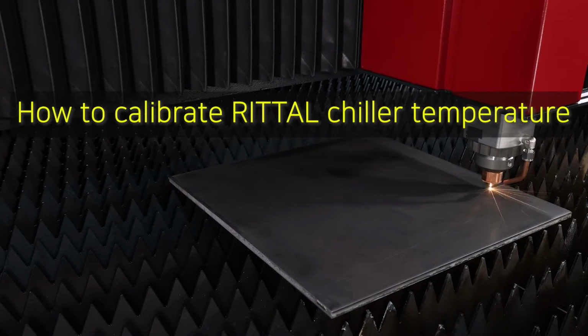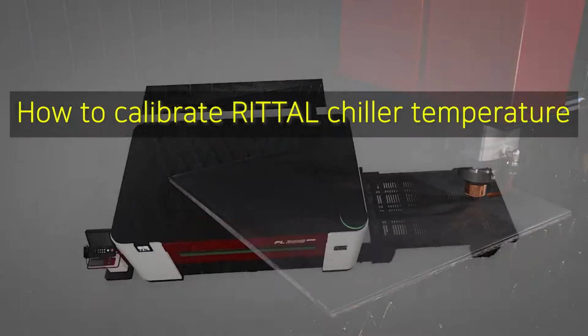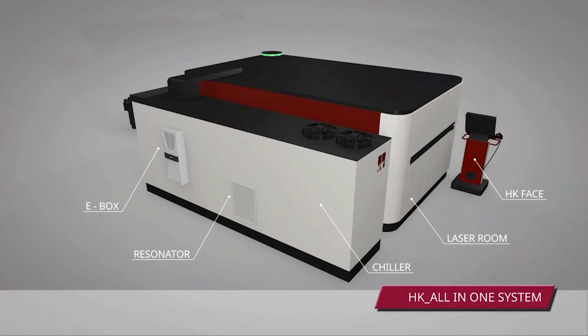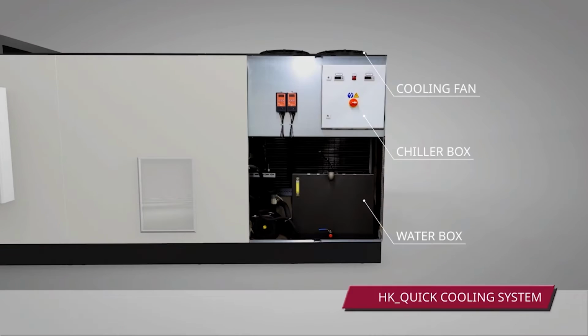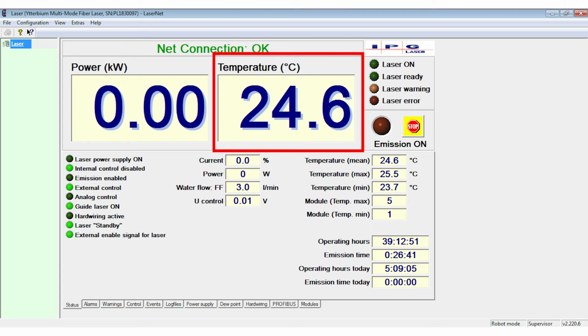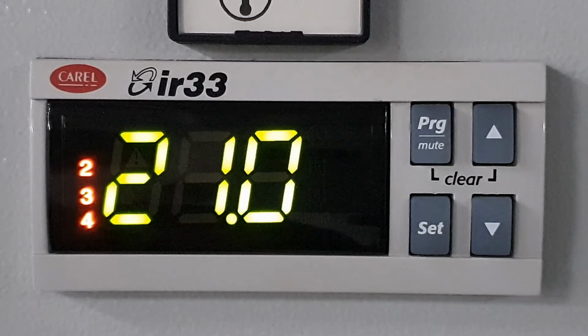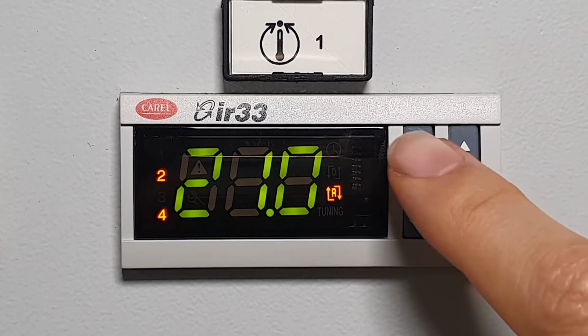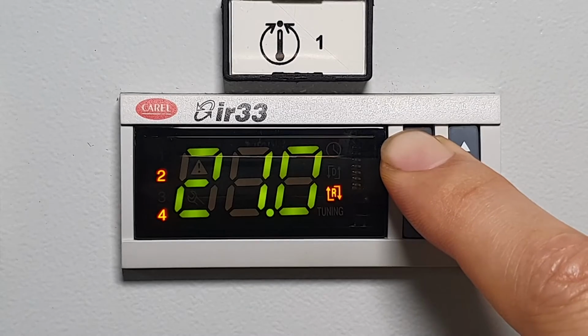This time, we will learn how to calibrate the temperature difference when an alarm occurs due to a difference in temperature between the chiller and the laser. When the alarm occurs, check the laser's temperature first in LaserNet. If there is a deviation compared to the chiller's temperature, press the PRG button until P1 shows up.